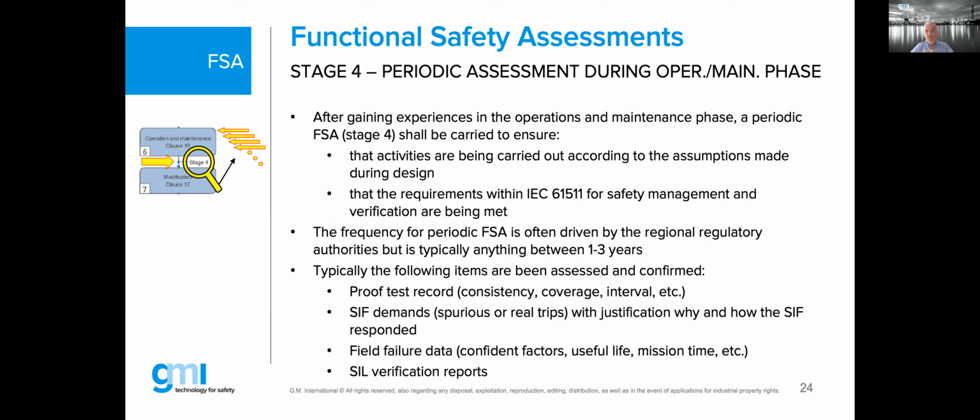What the regulatory bodies mainly drive around the world, and I give you a very typical and clear example, HSE, which stands for Health and Safety Executive, in the United Kingdom or Great Britain. They actually require every 36 months, or every 3 years, a stage 4 assessment on site of the end users. Because the regulatory body in certain countries has the power to force the end users to carry out such an assessment.